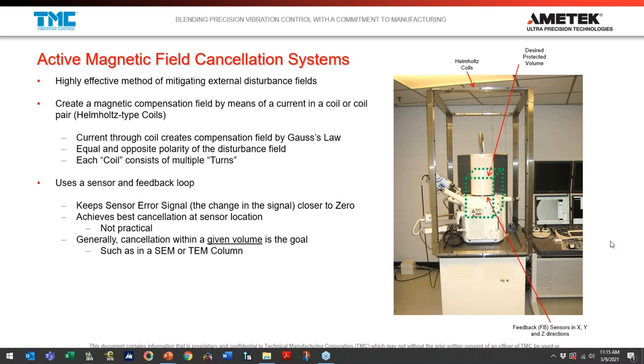Looking at the construction of these coils — what I call a Helmholtz coil freestanding cage or frame. In this frame, several turns of wire run in loops around each face. In this example, 12 loops of current-carrying wire run around the front face of the cage, with a matching pair of 12 loops on the back side. I create a six-sided box of coils. The second part is the sensor and feedback system — a feedback control system where a sensor is placed near the area where cancellation is needed, sensing the disturbance field.